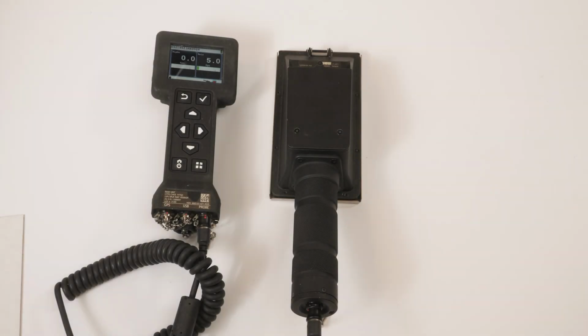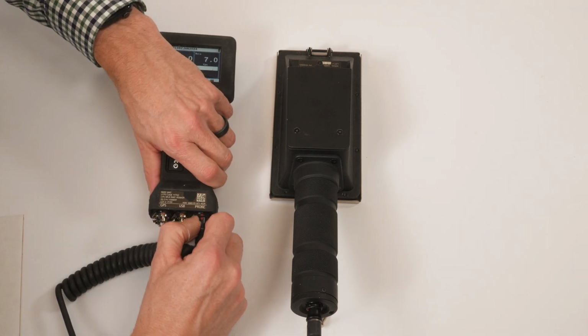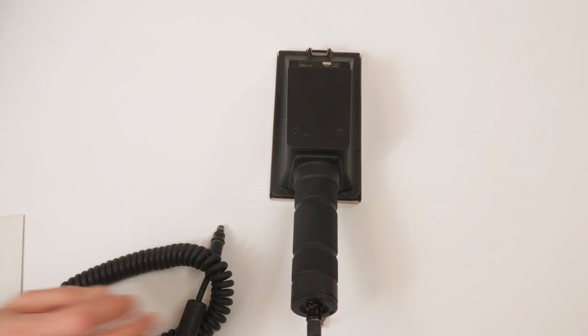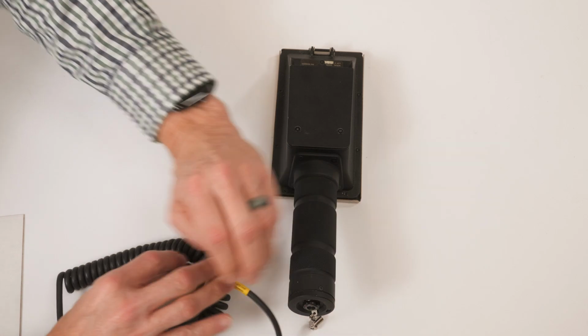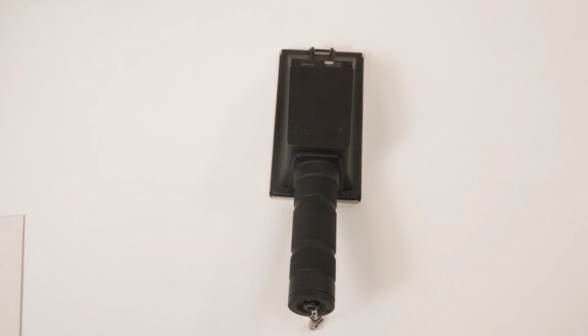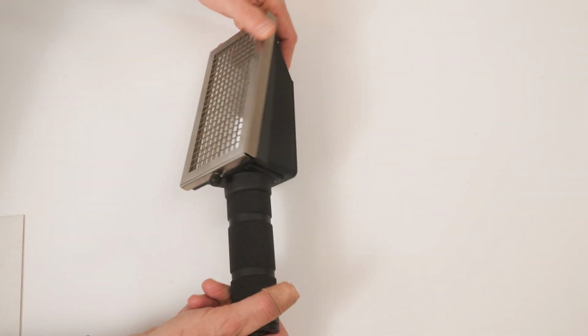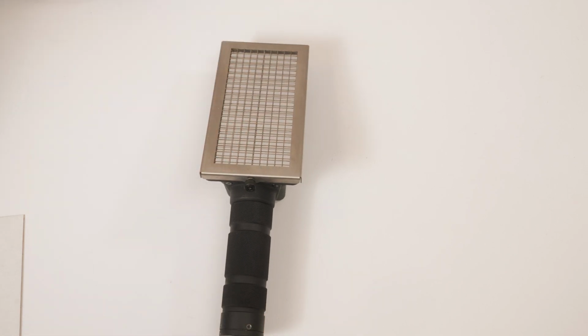Before beginning Mylar window and/or protective screen replacement, make sure the alpha-beta probe is disconnected from the base unit to prevent damage to the PMT, which is the detector inside the probe. Wait for at least 1 minute after disconnecting the common probe cable. Failure to comply may result in damage to the equipment. Full detection capability for the alpha-beta probe will not be ready until the scintillator that sits below the Mylar window has settled for 2 hours after exposure to light. Failure to comply may result in inaccurate readings.